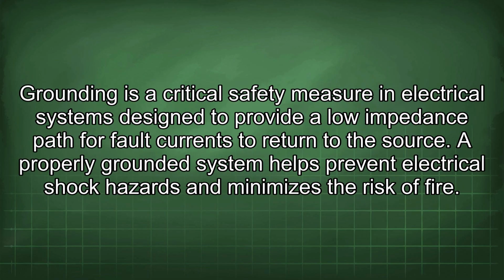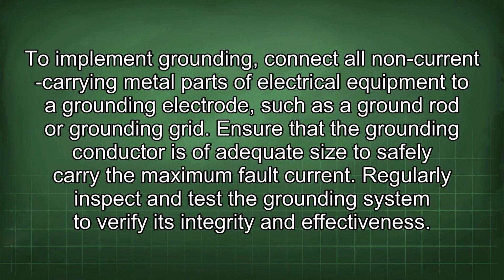Grounding is a critical safety measure in electrical systems designed to provide a low impedance path for fault currents to return to the source. A properly grounded system helps prevent electrical shock hazards and minimizes the risk of fire. To implement grounding, connect all non-current carrying metal parts of electrical equipment to a grounding electrode, such as a ground rod or grounding grid. Ensure that the grounding conductor is of adequate size to safely carry the maximum fault current. Regularly inspect and test the grounding system to verify its integrity and effectiveness.